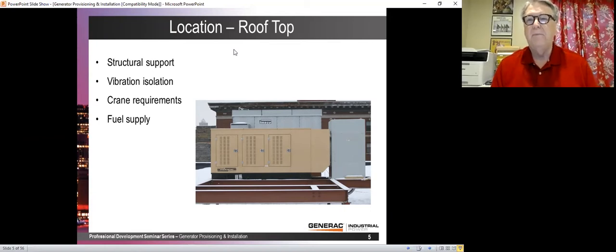But for me, even if it's 1 pound, I just say this thing needs to be checked by a structural engineer. And if it's a natural gas generator, then of course you can just pipe the natural gas up to the roof. And obviously I highly recommend natural gas generators for rooftop applications. That doesn't mean you can't have a diesel fuel on the roof, but if you do have a diesel fuel generator on the roof, you're going to have the tank down at ground level so they can fill it, and to keep lots of diesel fuel off the roof.